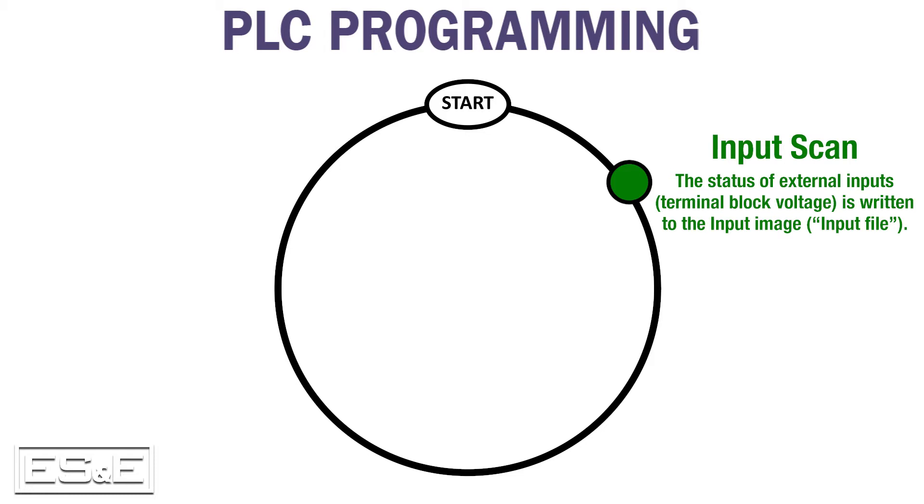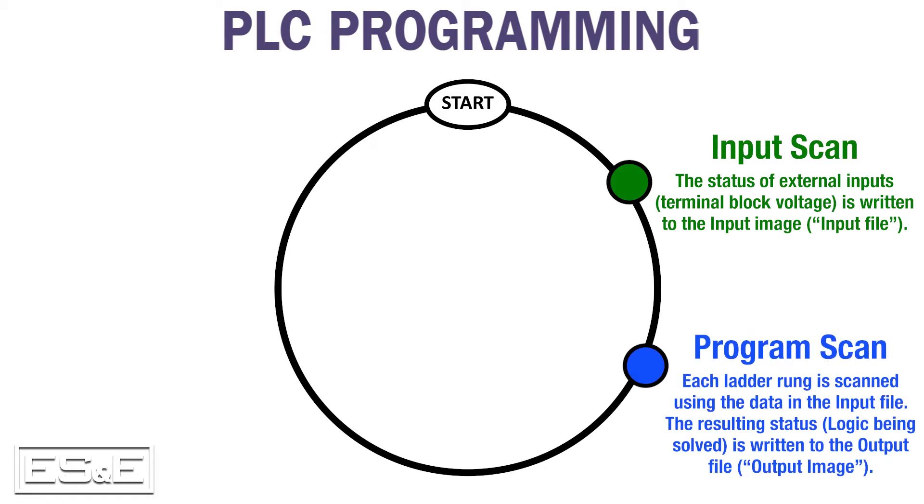During the program scan, the PLC uses the stored value of devices to solve the logic in each rung. If the logic solves true, the PLC updates the output image with a 1. If it solves false, the output image becomes a 0.